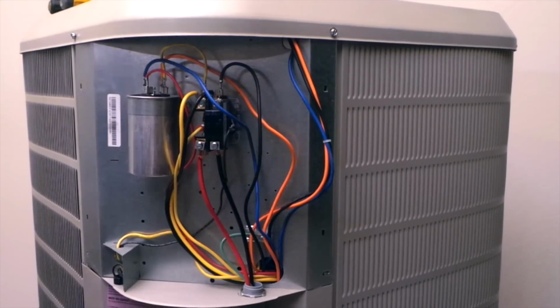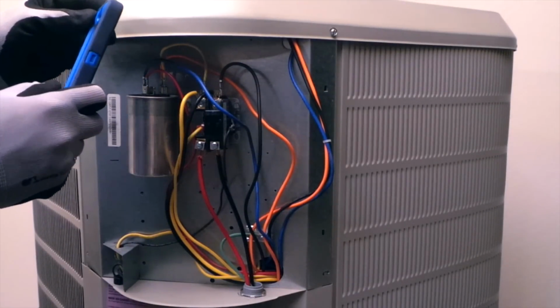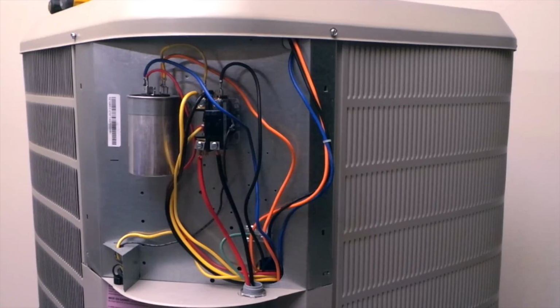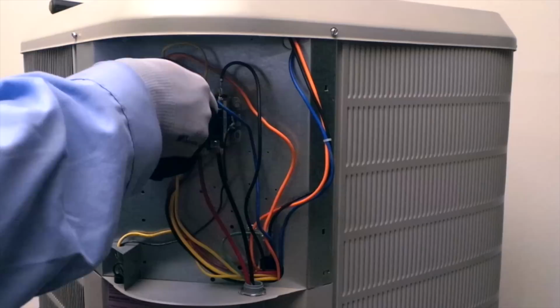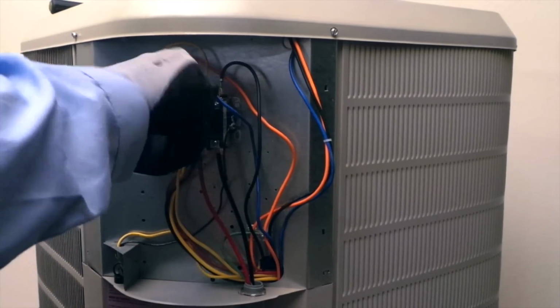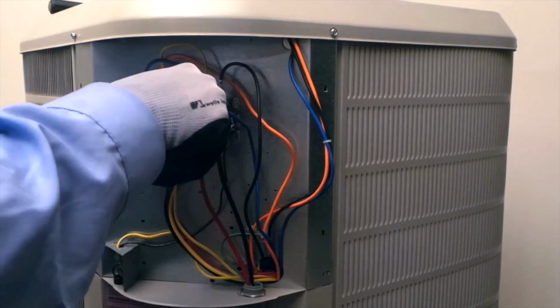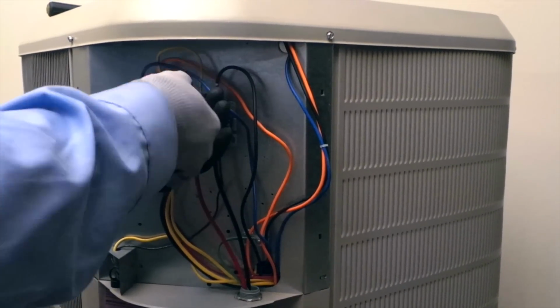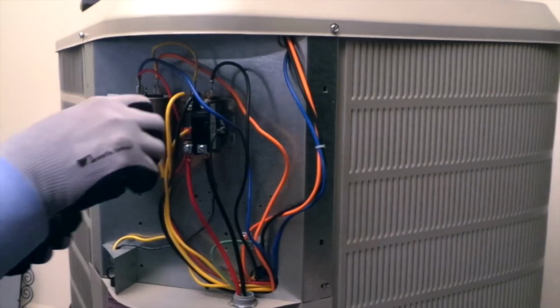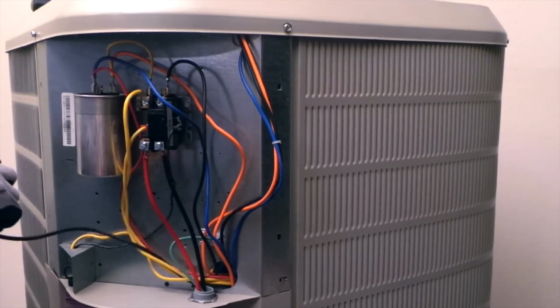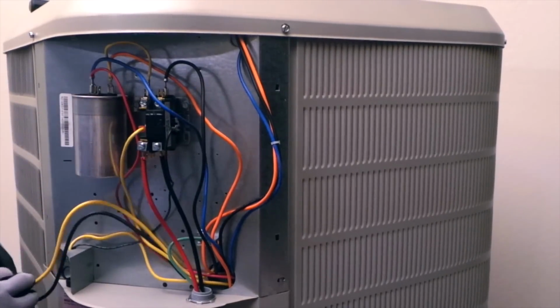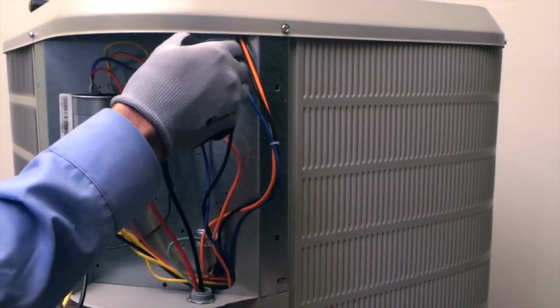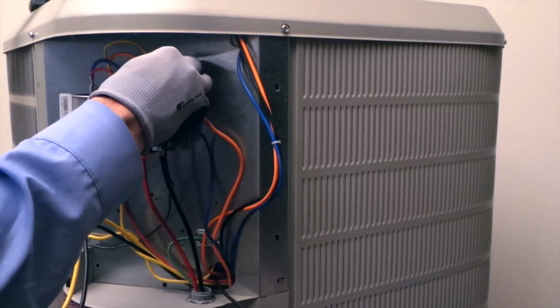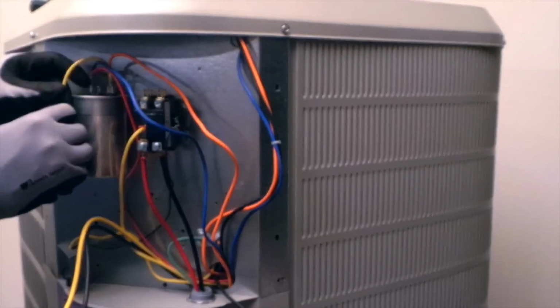Now it's time to start our contactor replacement. It's always good to take a picture for terminal location. If you notice, our contactor has lug terminals on the bottom and screw terminals on the top. We'll begin by loosening the screw terminals on the top of the contactor. Then we will remove the black wire, which is our common wire to our compressor, and then we will remove our yellow wire, which is our run wire to our compressor. Then our line voltage wire to the outdoor fan motor and the common wire to the capacitor.